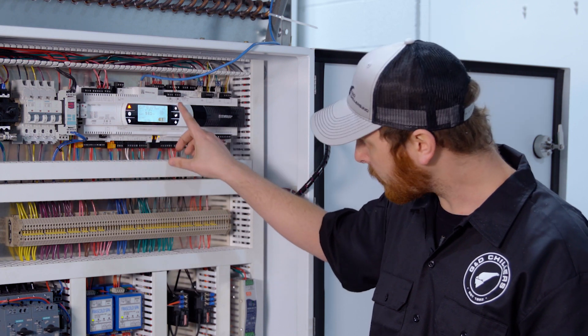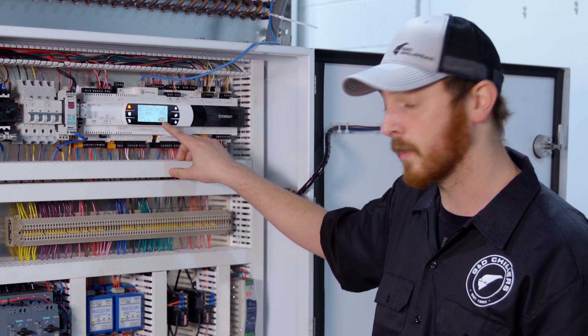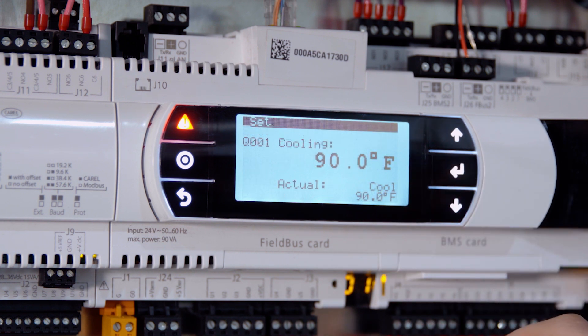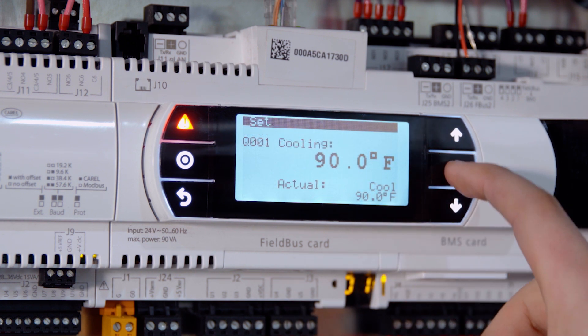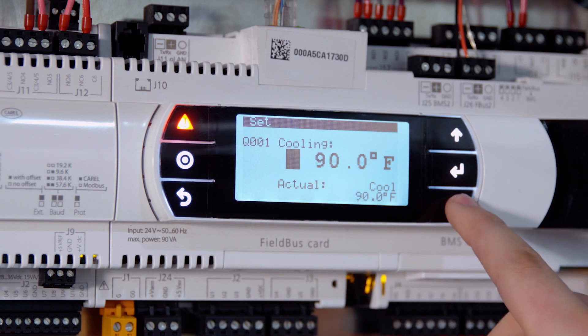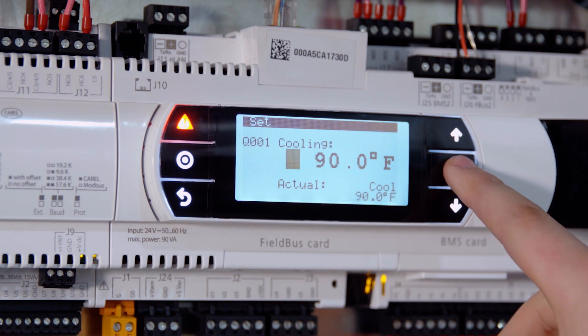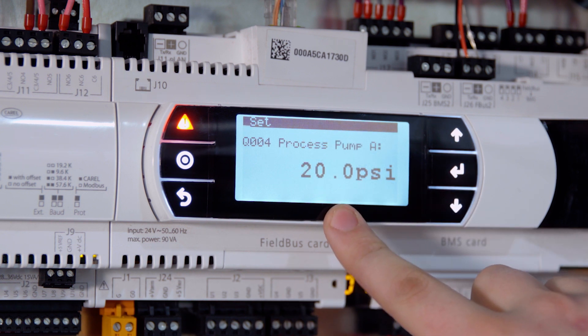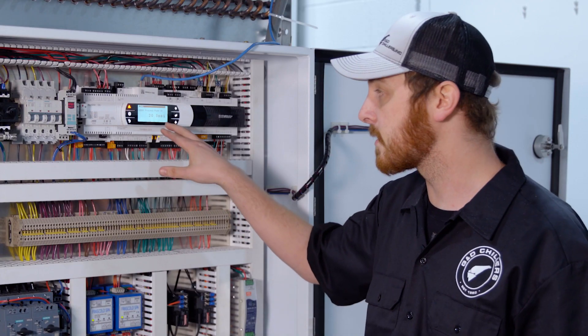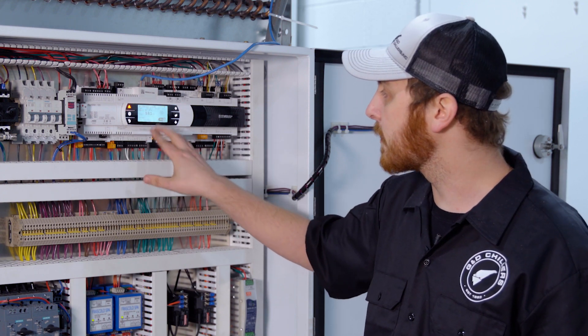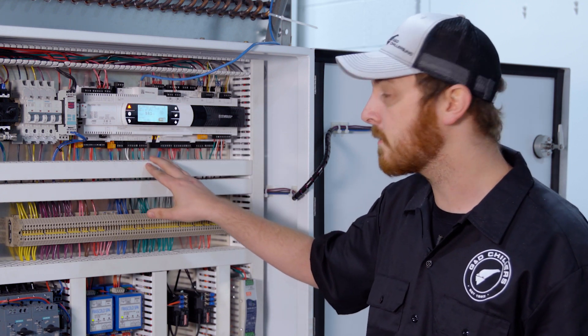On the main screen, if you go down to where it says 'set,' you can change two things. One being the set point — you press the enter button and it highlights next to the current set point so you can change it to your desired set point. From this screen, if you navigate down once and you have a chiller that uses a VFD, this is where you would set your desired pump pressure. Press the back button to return to the main screen, and if you have any questions feel free to give us a call here at the office.